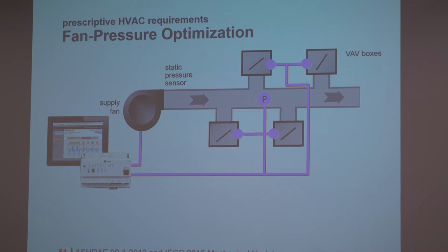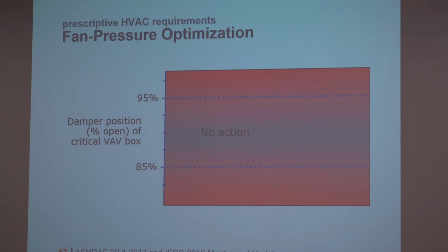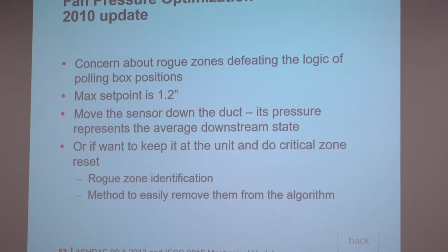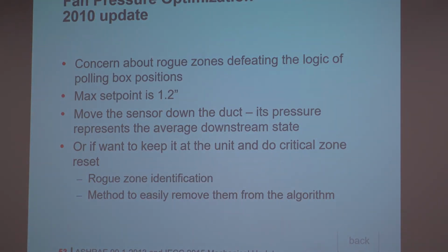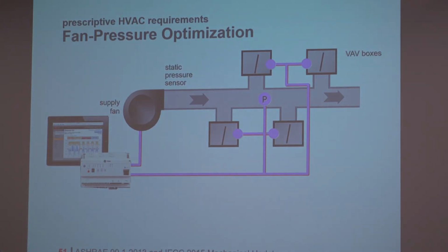So the new provision is that you have to identify where these rogue zones are and be able to eliminate them from the algorithm. The other option is that you can no longer set your DP, your differential pressure set point in your ductwork, so that its set point is any higher than 1.2. So that's the other option now, is either you put this little P where this purple P is, that's where the differential pressure pickup for the duct is, and the engineering standard was sort of like 2/3 of the way down the duct on the critical run.